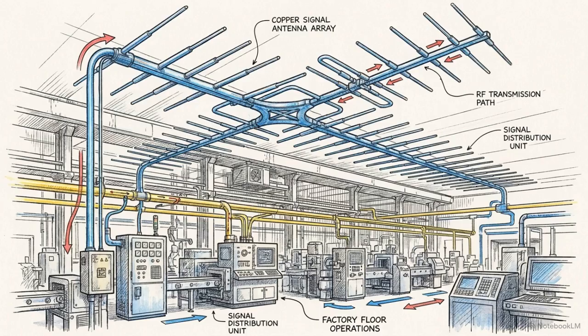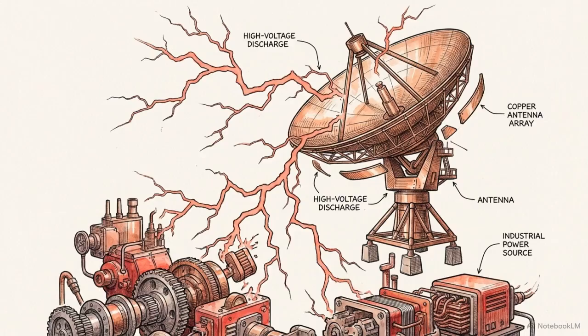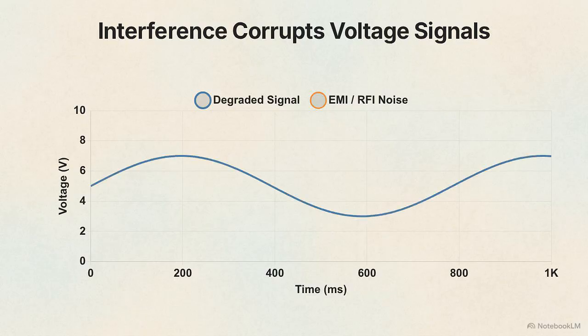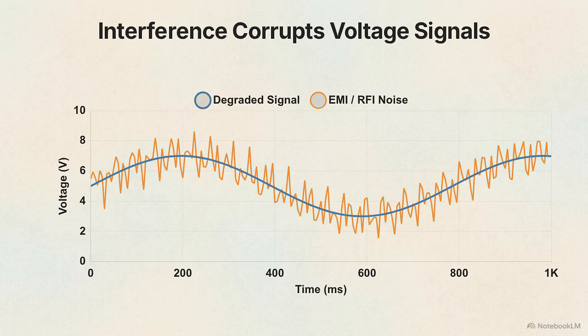To accurately read a voltage signal, the receiving controller also needs a high input impedance. That effectively turns our thousands of feet of copper wire into a massive antenna. That antenna easily picks up all the ambient electrical noise from the factory floor, which layers high-frequency spikes right on top of our already degraded signal. Between the signal decay over distance and the absorption of stray electrical noise, voltage signaling fails in heavy industrial applications.